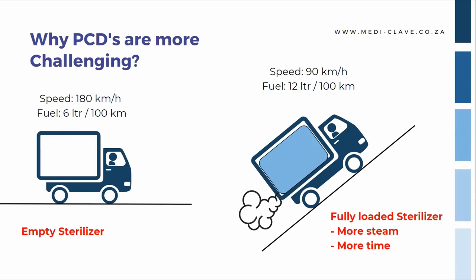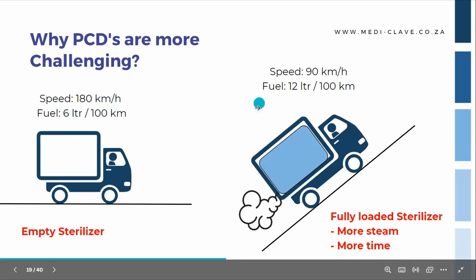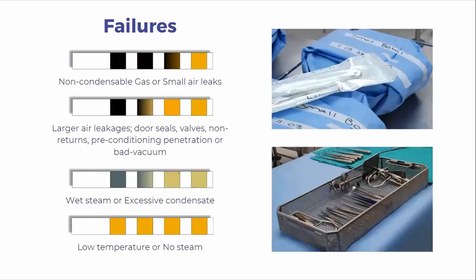So on the left, that is the Bowie-Dick testing here, whereas your PCD is testing here. The Helix device usually picks up failures before test methods and even before technical engineers can. In Germany, the Helix device for Bowie-Dick and batch monitoring has been in use for over 25 years. And in Holland, Dutch hospitals have been using Helix devices as a Bowie-Dick and batch control since 2004. Since 2009, the EN285 A2 recommends the use of a Helix as an alternative for the Bowie-Dick test pack, which is mainly for sterilizing instruments.